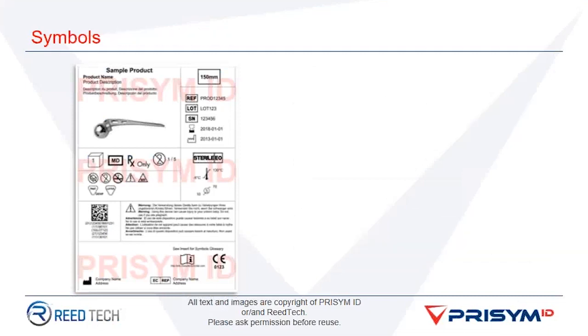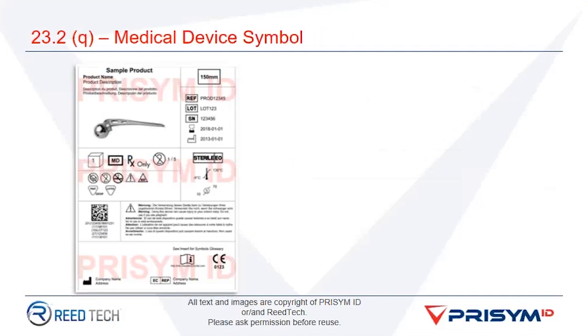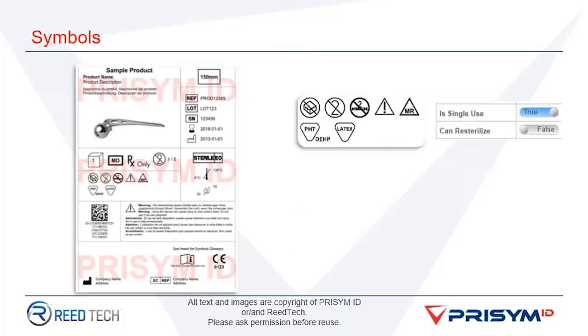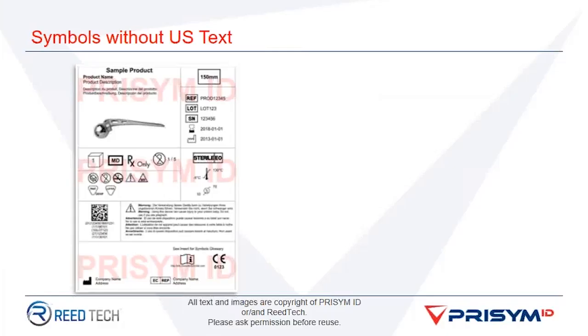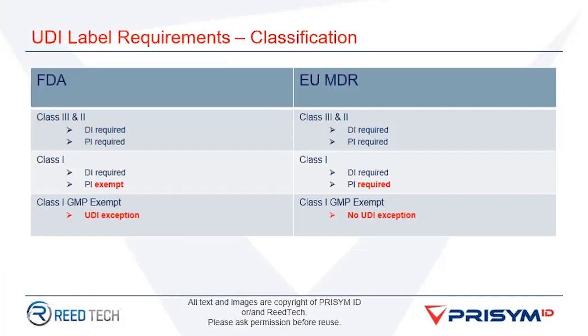There are some exceptions for direct marking, with it being technologically not feasible. So that is an exception that you could consider. The other exception is for a situation where applying that direct mark would cause a decrease in the safety and the effectiveness of the product. So those are two that you could evaluate and claim.